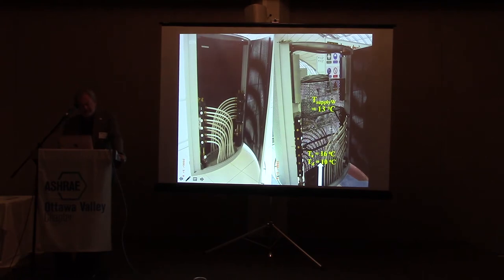But what was decided was to put in the manifold for the distributor to the different circuits inside the supply diffusers, because the air coming in here would be 18 or 16 degrees, and the dew point was 10 degrees. The goal was to keep a dew point of 16 degrees in the air. So it's still 5 degrees lower than the minimum floor temperature of 21. And to do that, they had a supply at a dew point of 10 degrees, which is lower than the supply water temperature of 13. So you have no risk of getting condensation. And that's why you avoided the cost of having insulation on the pipe.